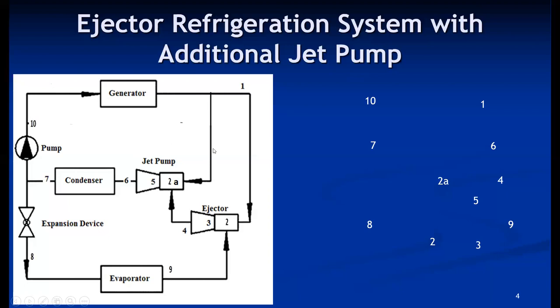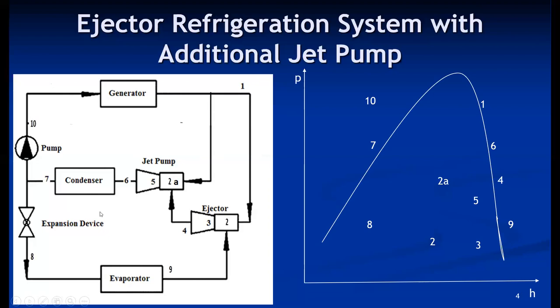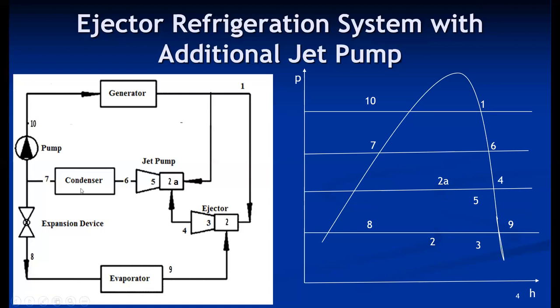Now we will discuss the thermodynamics and cycle working of this system using a pH diagram — that is, the pressure-enthalpy diagram. In this pH diagram, there are four pressure lines: first, the evaporator pressure, which is approximately the same as the ejector suction pressure; second, the jet pump pressure (the second ejector); third, the condensing pressure; and fourth, the generator pressure. This is also called a four-pressure system.